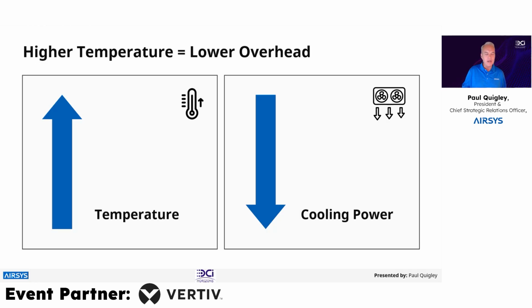Thank goodness NVIDIA announced the 45C, but we've done testing, and multiple companies have done testing up to 55 and even 60C for the inlet temperature for the chips. What that does is dynamically release a lot of energy consumption, because we can begin to eliminate compressors on data centers. If we can start eliminating compressors on data centers globally, we release a new potential power in the ranges of anywhere from 40 to 60% power gain with our existing structures. That's a dynamic transitional difference we can see there.